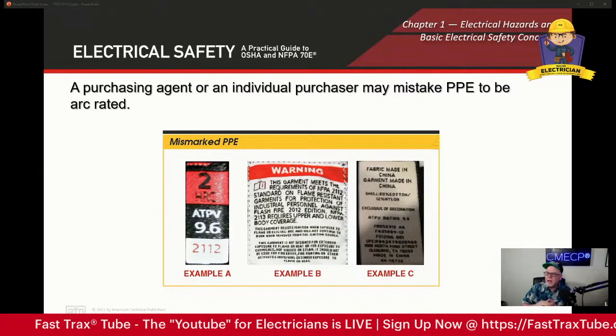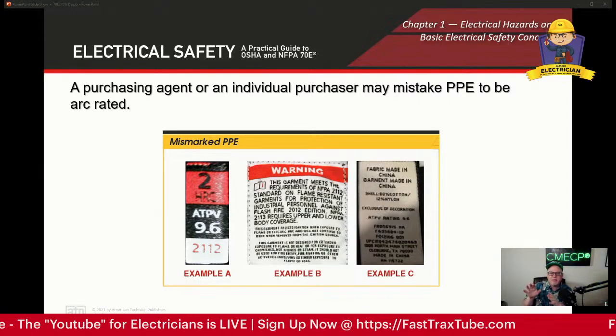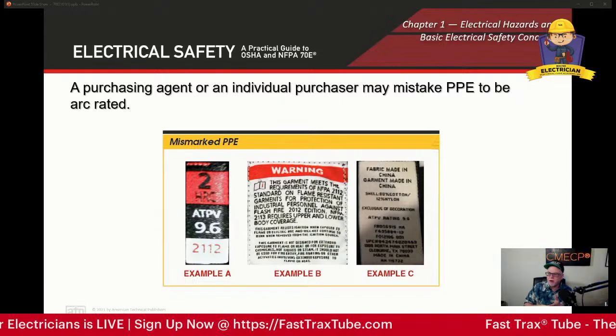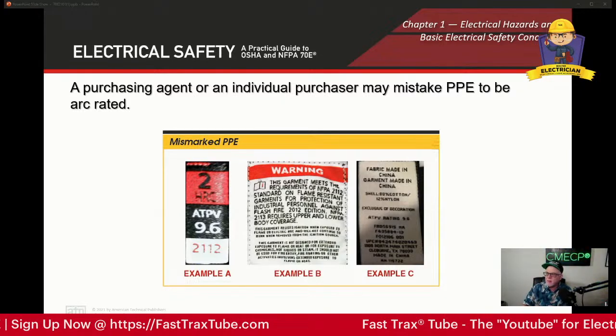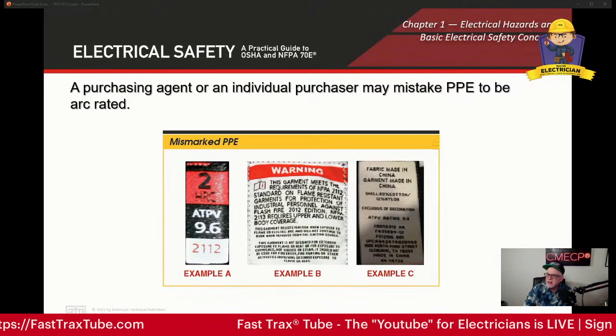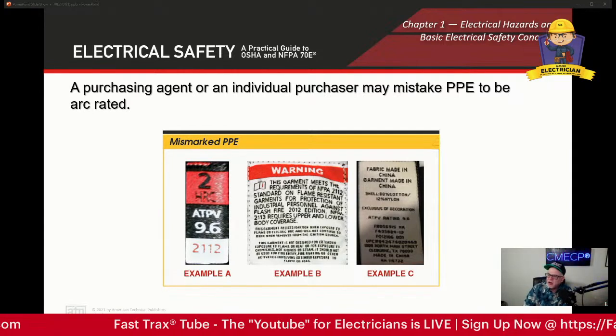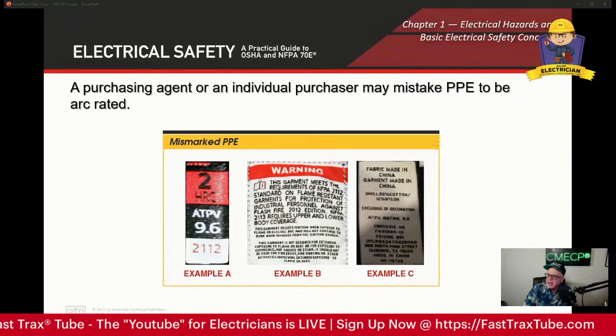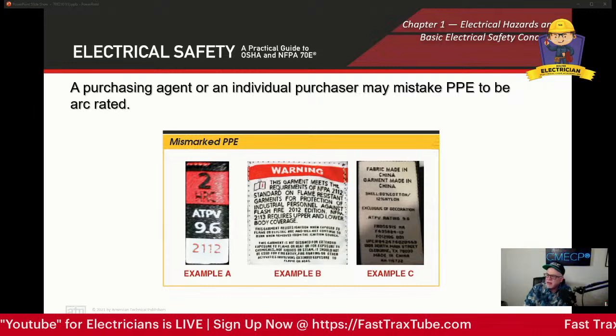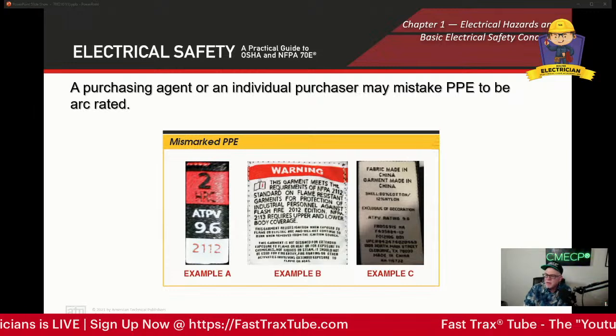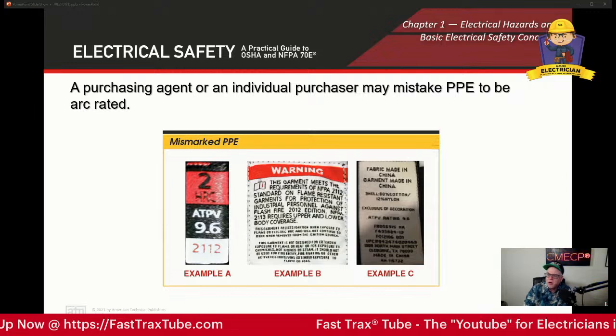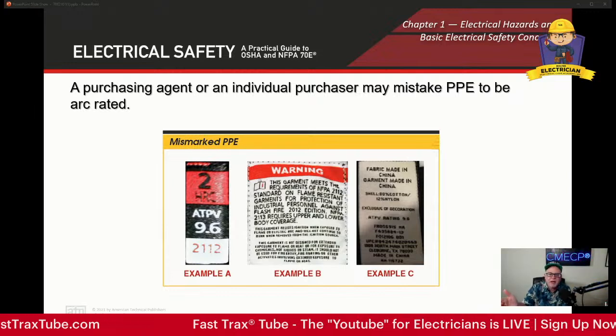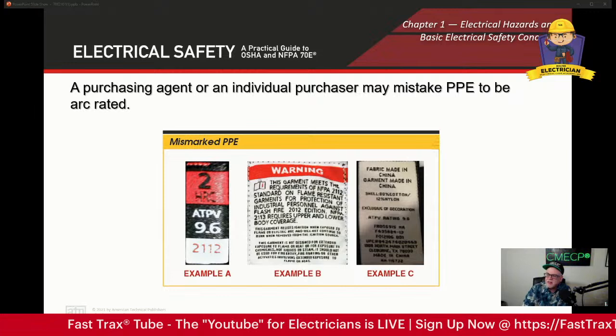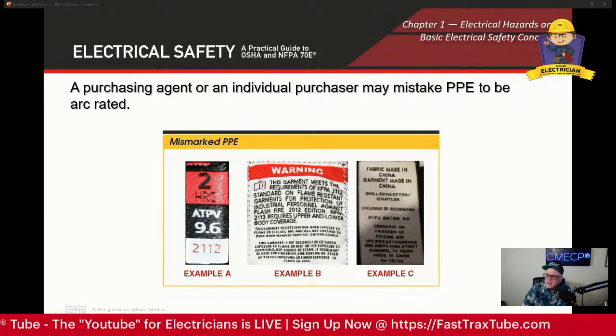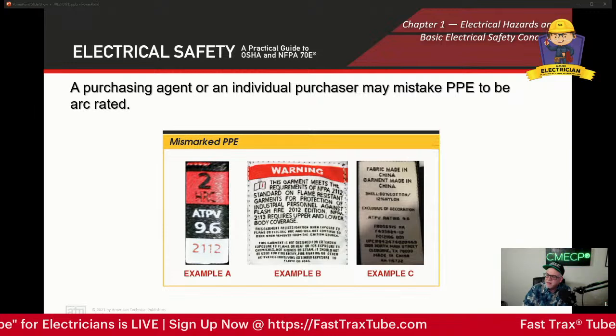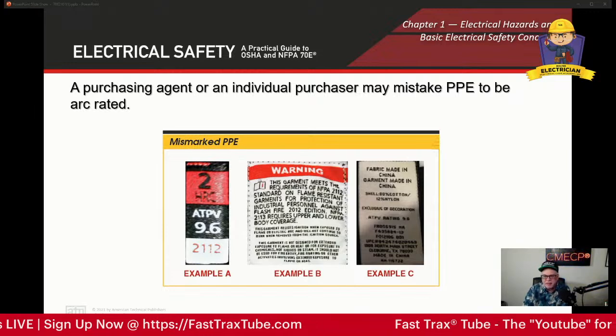So if you're looking at this material that you're buying from somebody, be aware of the mismatch. In this example, look at A. Example A clearly has an HRC2 rating and a 9.6 ATPV rating on the pocket label. It also shows NFPA 2112, but it says nothing of NFPA 70E or ASTM F1506.